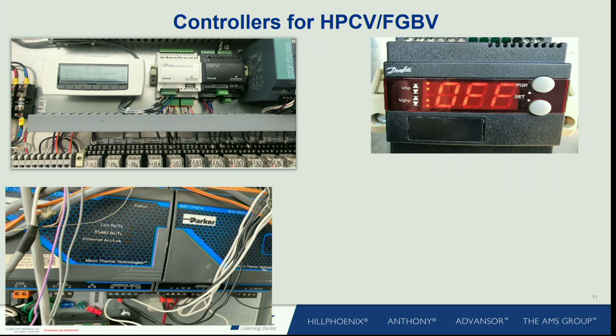So now they can't get the chip, there's a couple options. Paul Burnett and I are having disagreements - I'm a fan of the 722, that's the Danfoss controller used for mini boosters, but it has an analog output, and I put a 208C board, which is a stepper valve driver, and tie that to it. Now I can do the same thing as the 326A, and I'm still doing it per the Danfoss original algorithm. And the other suggestion, you can do a 781, but you have to add a 103 and a 208.